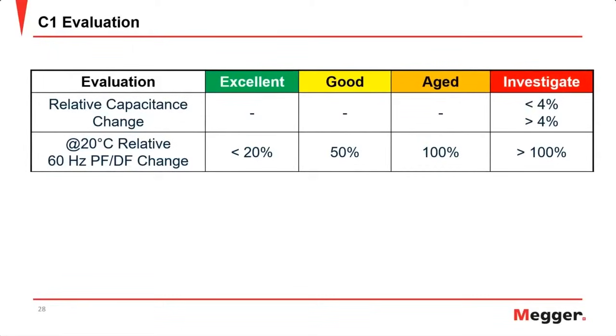So we look at the bushing nameplate and we see that it has a power factor. If the change is less than 20%, then we consider that bushing to be in excellent condition and not aged since the last time or since it was manufactured. A change of up to 50% would be good. A change of up to 100% would be service aged. But any time that power factor doubles compared to the nameplate would be a reason to investigate.